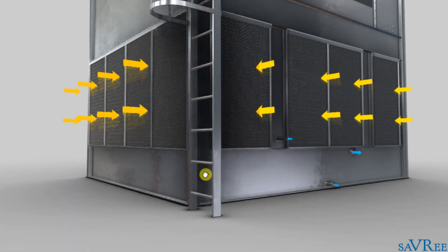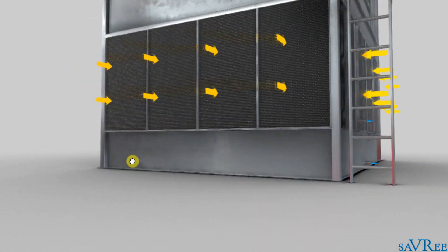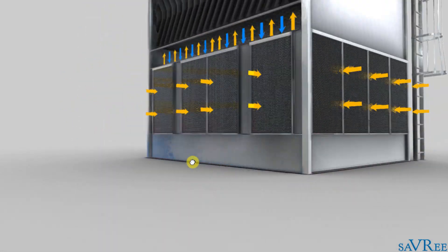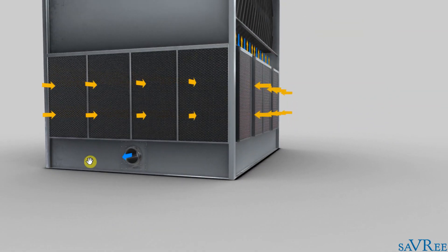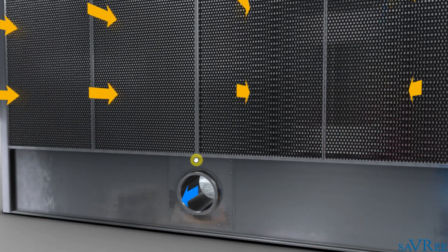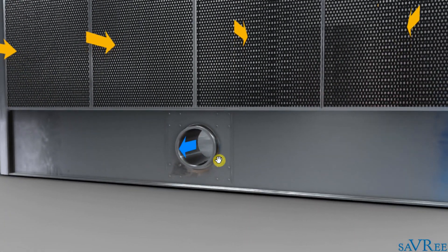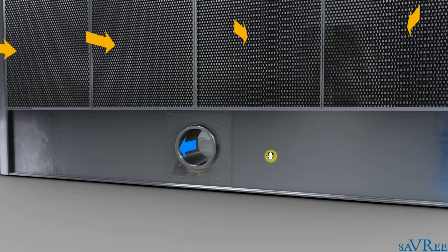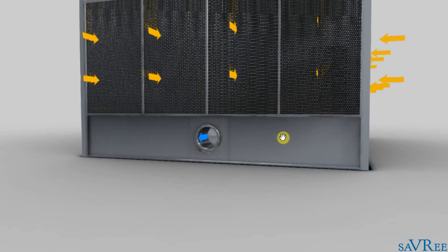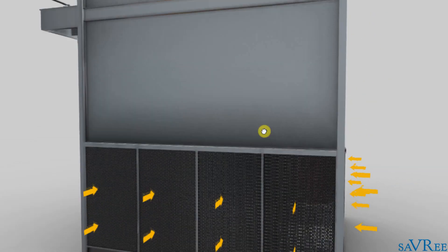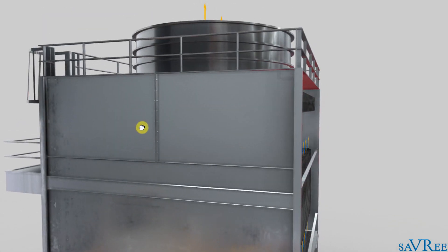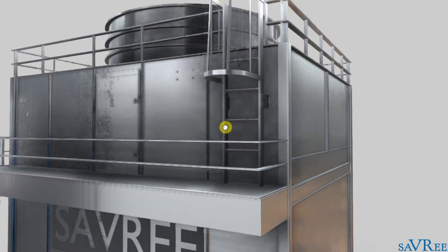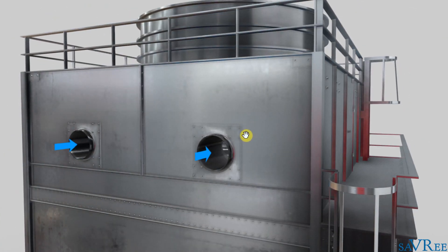And then we are going to suck the cooled cooling water out of the base. And we can see that happening here. That would be a discharge from the cooling tower. And if the cooling tower is working correctly, then we're going to have a temperature difference between the discharge pipe here and the inlet pipes at the top of the cooling tower, which are around the opposite side. This temperature difference is actually known as delta T, so a relatively simple process for the water.